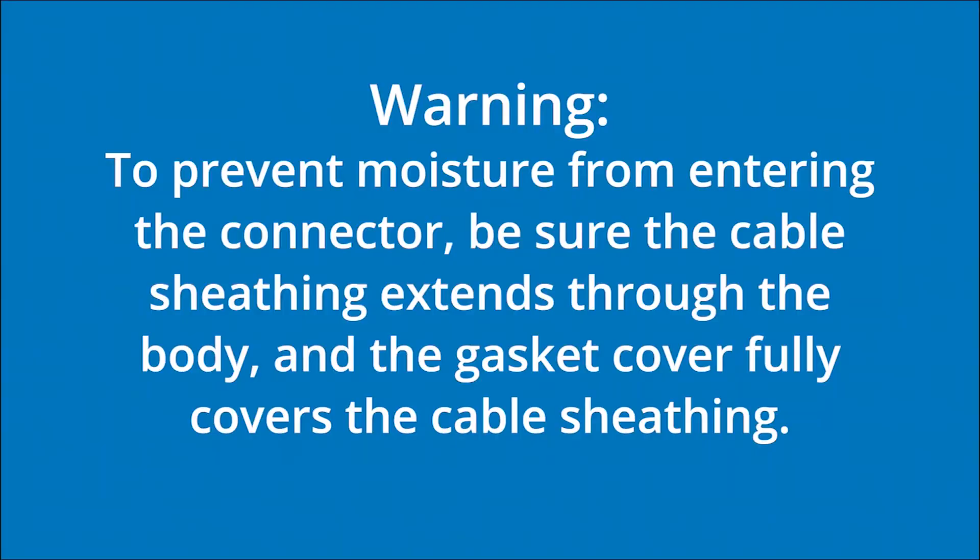To prevent moisture from entering the connector, be sure the cable sheathing extends through the body and the gasket cover fully covers the cable sheathing.